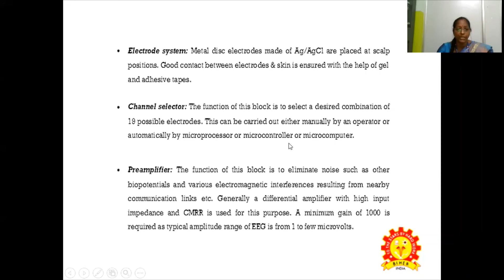This is calibration. This block has to calibrate the display or the recorder for a predetermined amplitude. For example, a sine wave of 1 millivolt is generally used for this purpose. Isolation: the patient should be isolated from the high voltage power section by the low voltage patient section.